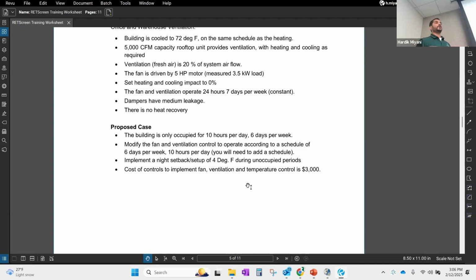When is the building going to be occupied? At what time are your tenants going to be in the space? Suppose the tenant will be coming at 8 a.m., and you want the system to reach 72°F by 8 a.m. Now the building management or the controls will calculate what your heating or cooling load is, what the outside temperature is, and estimate how early I need to start my system to reach 72°F by 8 a.m.